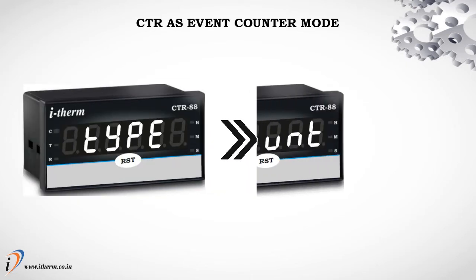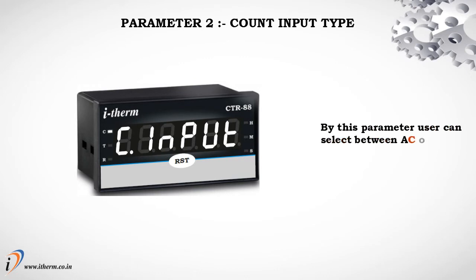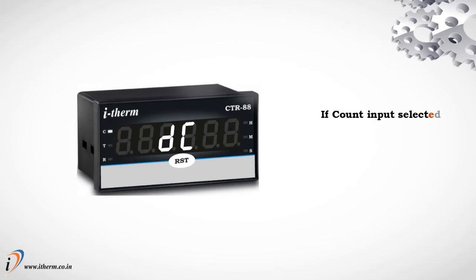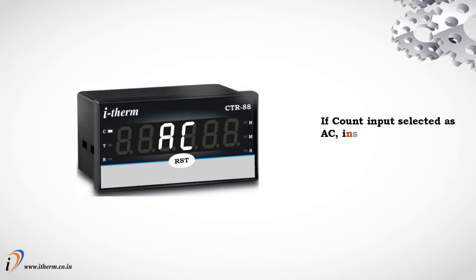CTR as event counter mode. Parameter 2: count input type. By this parameter, the user can select between AC or DC as count input. If count input is selected as DC, the instrument will count pulses from a proximity sensor or by potential-free contact. If count input is selected as AC, the instrument will count pulses from a 230-volt AC supply.